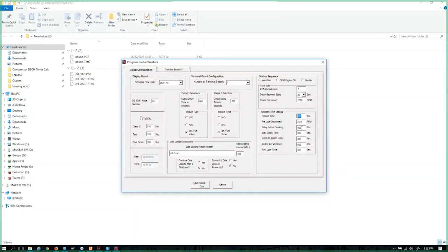And then we do a delay before cranking. So watch out for this terminology. Prelube time is the ultimate time this system will prelube. Delay before cranking is how long it will prelube before we send a crank signal. So let's say 30 seconds. We're going to prelube for half of the 60 seconds, 30 seconds, before we engage the starter. Now the starter is linked to output module 3. So now it's turned on in this auto sequence, but we tell it how long we want it to stay engaged. I'll say 15 seconds for this exercise. So now we're going to crank up to 15 seconds. Once we start cranking, we set the crank to ignition delay. That's how long we want to crank and purge any unspent fuel out of the system before we turn on our ignition. I'll use 2 seconds.